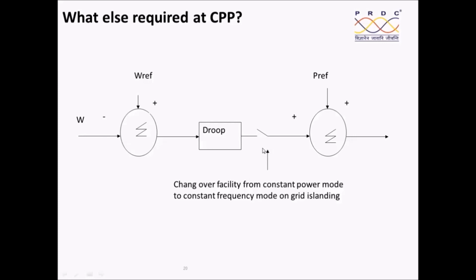Therefore, in the governor loop, there is a changeover switch which is going to change the governor control from the constant power mode to the constant frequency control. What is very important here is, as soon as the islanding breaker operates, the signal should be taken.